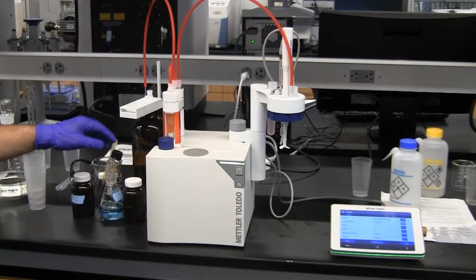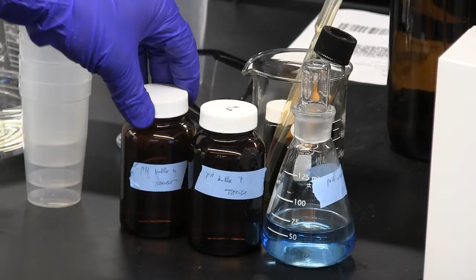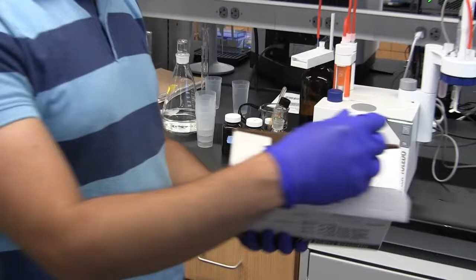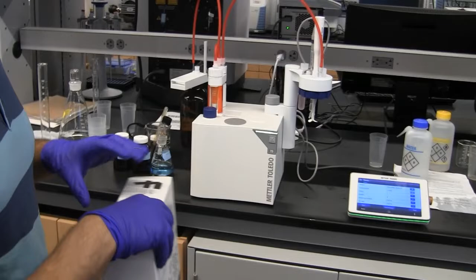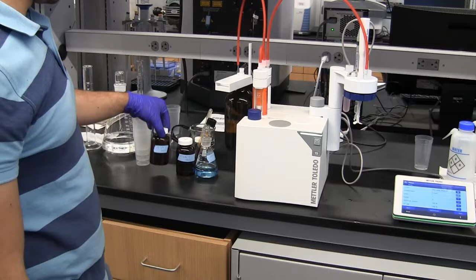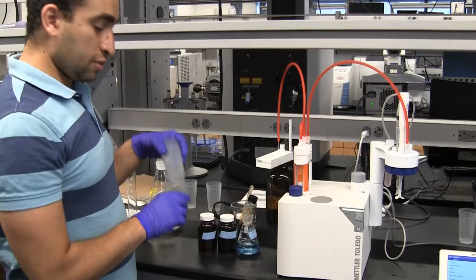In order to calibrate the system, we have 3 pH buffers: pH 4, pH 7, and pH 10. And generally we have a new batch of them, as I said in the beginning, in this pack. But we will keep reusing them until they go bad. So try not to use the new ones because we don't have much of it. So just keep reusing those until one of them goes bad, and then we renew it from the new batch. So get new caps.